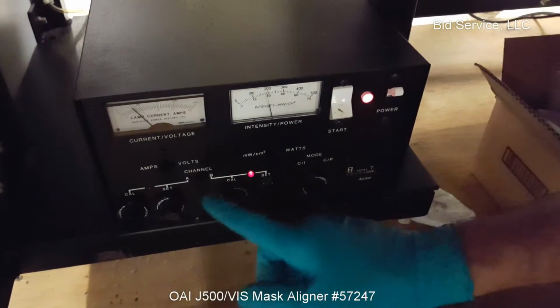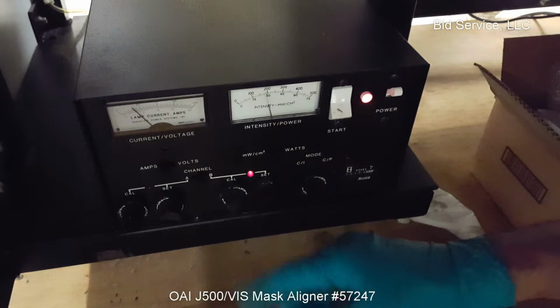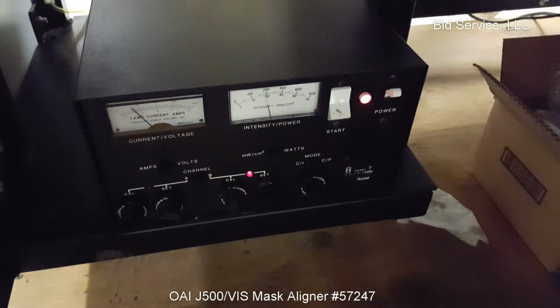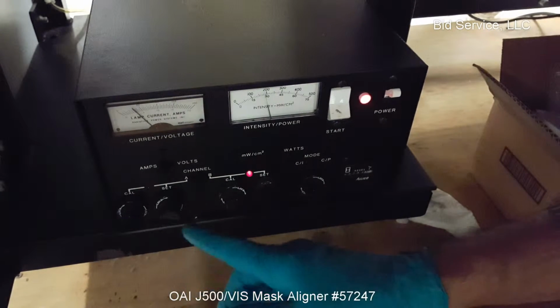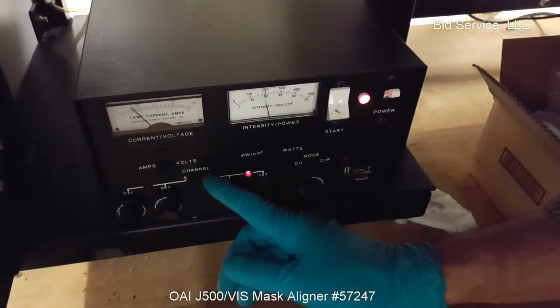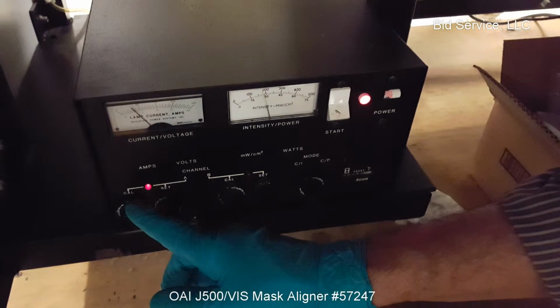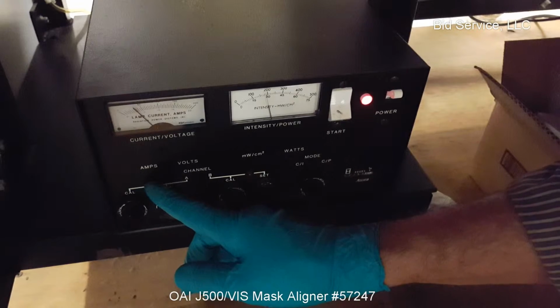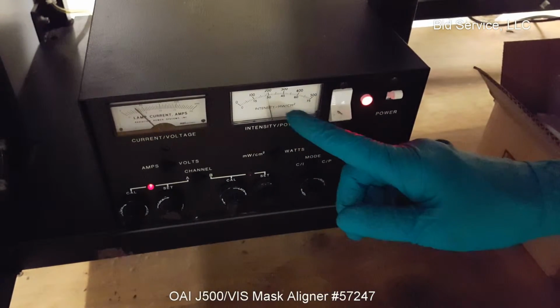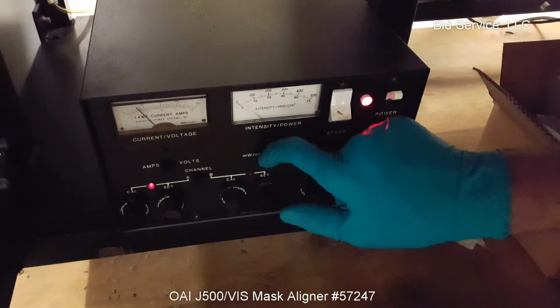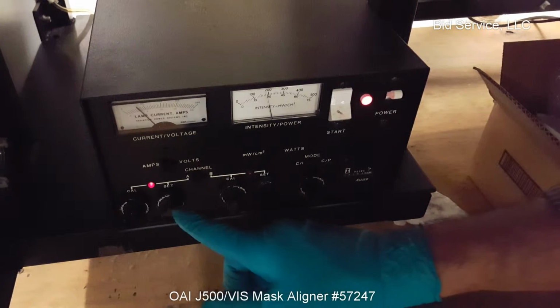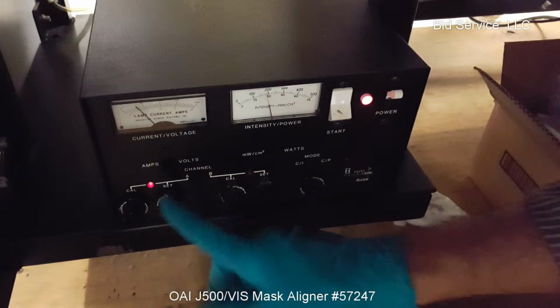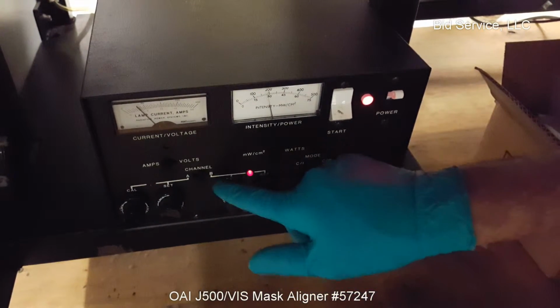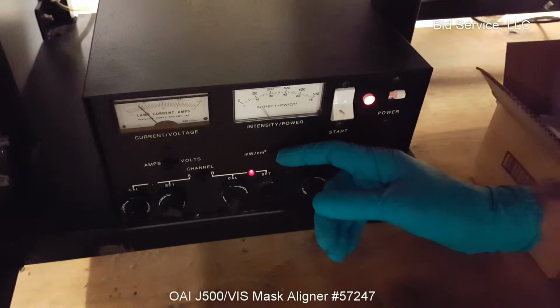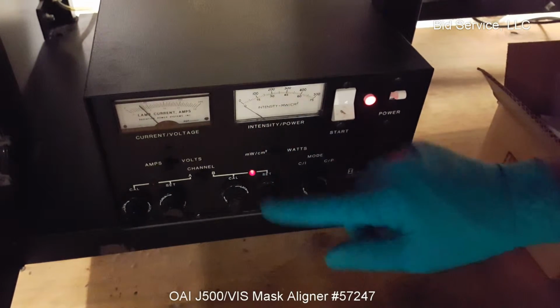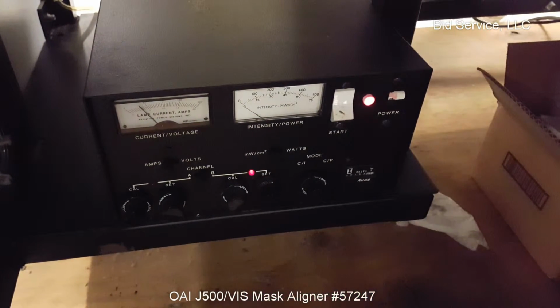Each channel, A and B, can be defined and calibrated using an external meter at the mask surface or at the level of the substrate. We have to select channel A and measure the intensity with the shutter open at the substrate level, and adjust the calibration pot to match the intensity reading on this meter to the external meter. If the detector on that external meter is 365 nanometer, then channel A is 365, and channel B can be selected, and the intensity should be measured at 400 or 405 nanometers and calibrated using this calibration pot.